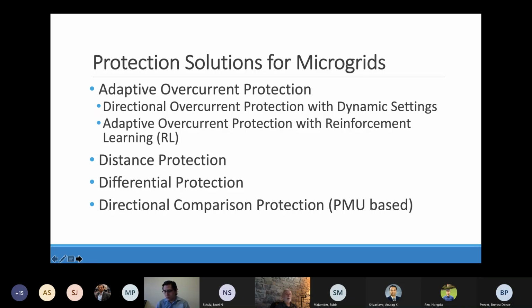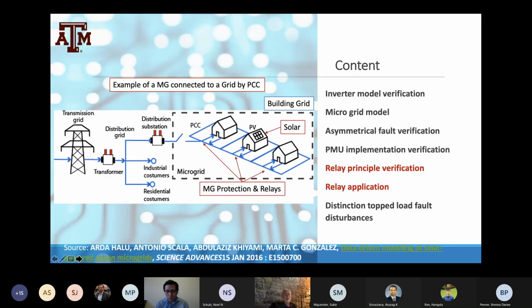Then differential protection, of course, would be great, but the physical distance between the ends of the zone that differential protection would be covering is really limited. So it is something that we shouldn't really consider as feasible unless the microgrid is in a rather small area. And then directional comparison protection, which is based on phasor measurements, Jorge will say a few words about towards the end of his presentation.